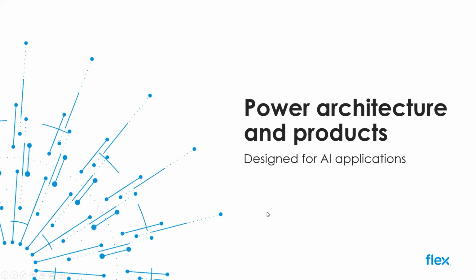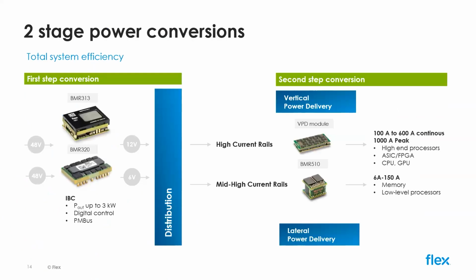Thank you, Ola. Let's take a look at some of the different power architectures employed in this area for AI. You touched there on the first stage conversion and second stage conversion. If we take a step back, one of the things we've seen really grow in popularity as the power levels have increased per rack is the change from a 12-volt backplane to a 48-volt backplane, nominally 48 volts, typically in the range of 48 to 54 volts. That increase by 4 of the supply voltage decreases the current by 4 and the losses by 16. So it's a huge benefit for server manufacturers and AI applications to move towards 48 volts. As I mentioned at the start, our legacy and history is in 48 volts, so we have a lot of knowledge and capability in this area.